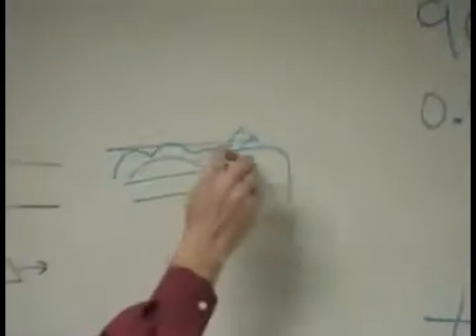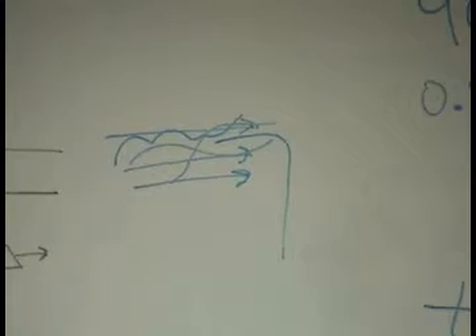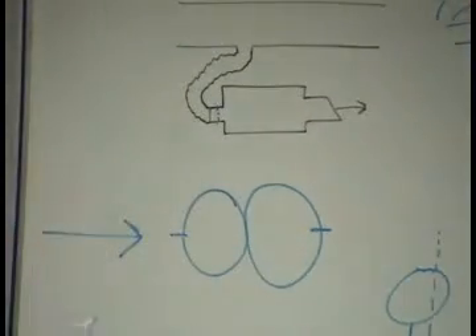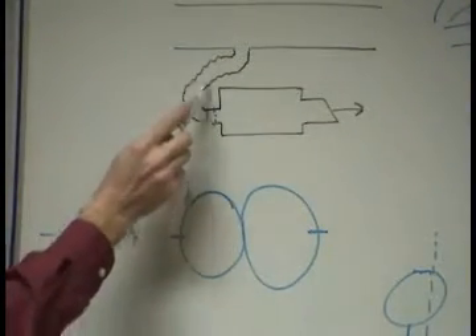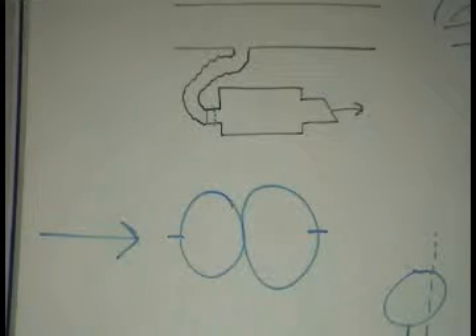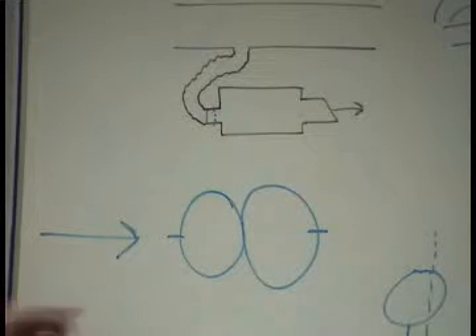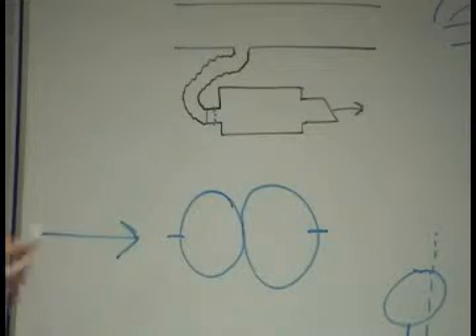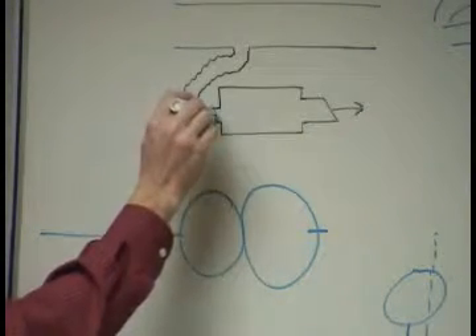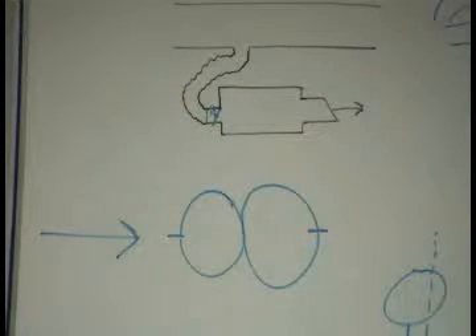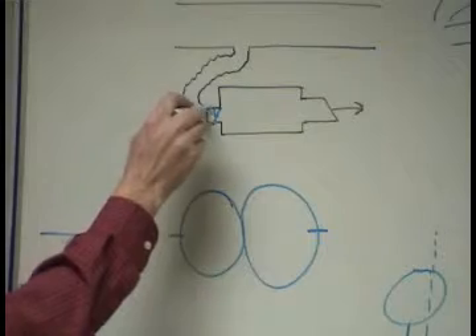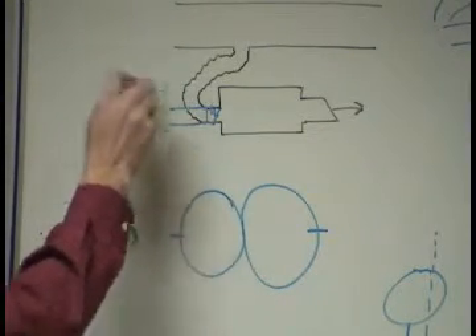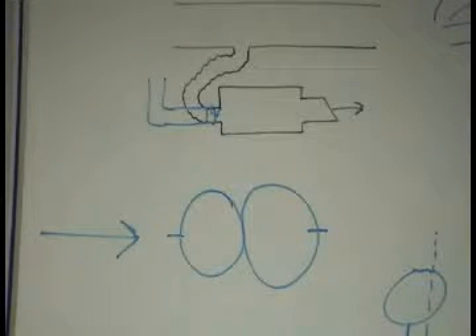If this area is swirling around, when it goes by there, that differential pressure is going to be whacked and it's not going to be accurate. So we've all seen this installation, right? Trunks come down, they got flex, usually about 13 foot of it. It's pinched off right there at the opening because the light was right there, so they had to cram it in there to make it work. And you've got no straight duct. Here's our pitot tube right here. Here's our damper right behind it. There's nothing straight about any air anywhere near there. So if we can get a little bit of straight air before that box, you've got half a chance of getting a decent reading.